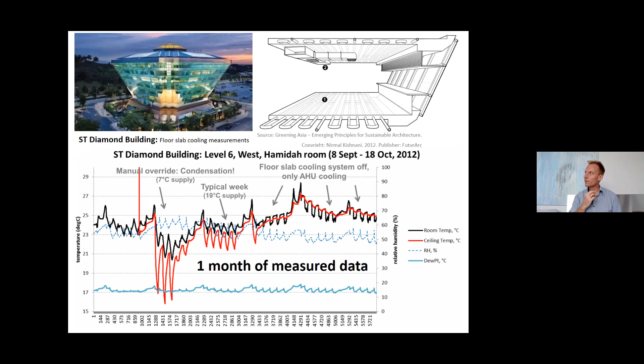So for the Green Tech Malaysia building, we looked at our instruments - temperature good, humidity good. We didn't measure air velocity, so we thought everyone should be thermally comfortable, but that wasn't the case because people couldn't feel the air movement. For the Diamond building, we corrected that by sizing the AHUs normally so they produced the same air movement, but regulated the coil temperature so they gave off less cooling. We still saved on cooling, but the air movement was close to what you'd normally expect in an office building in Malaysia.